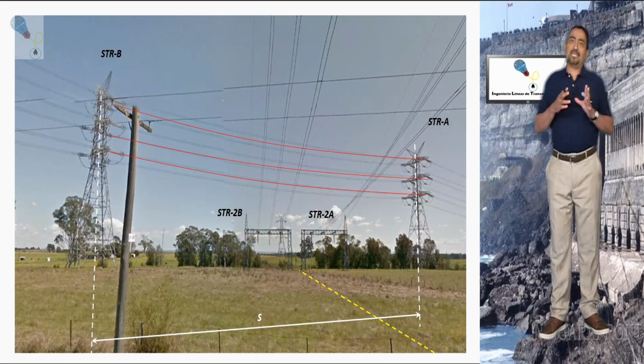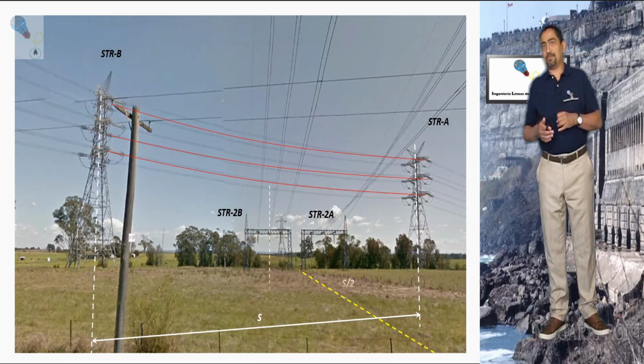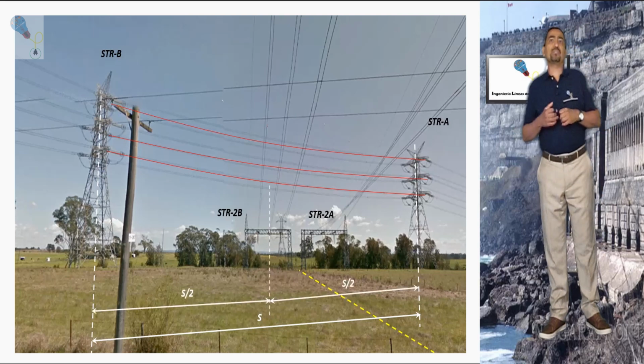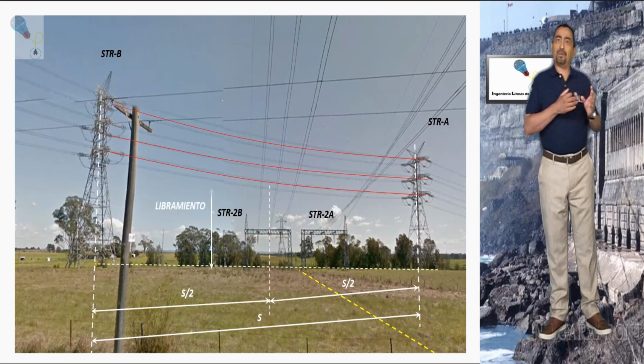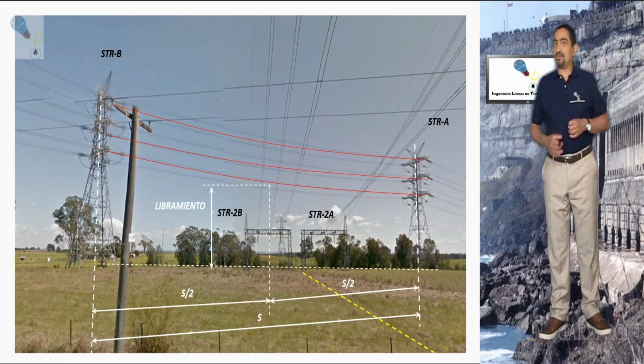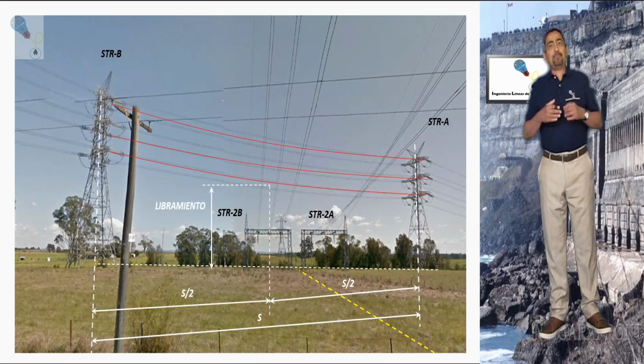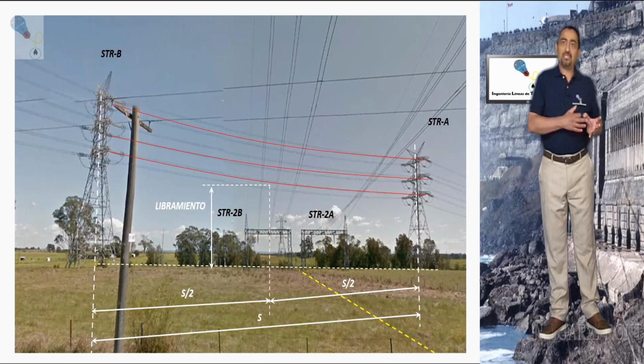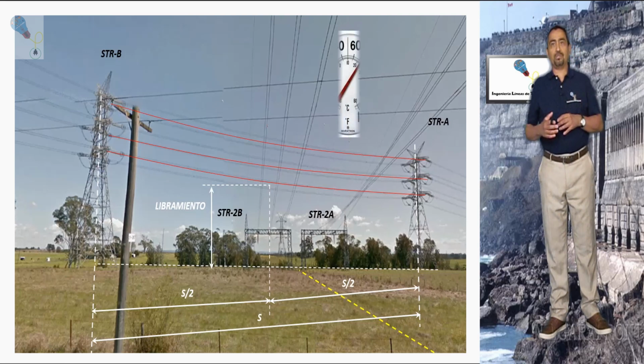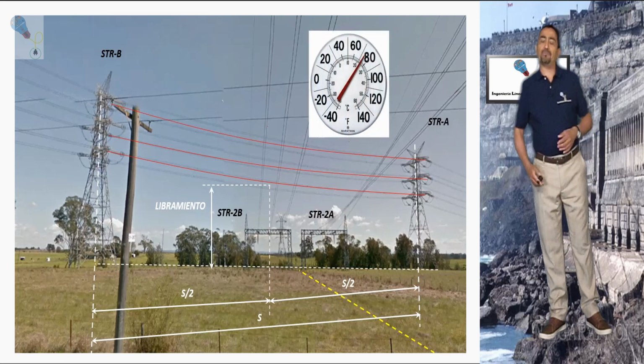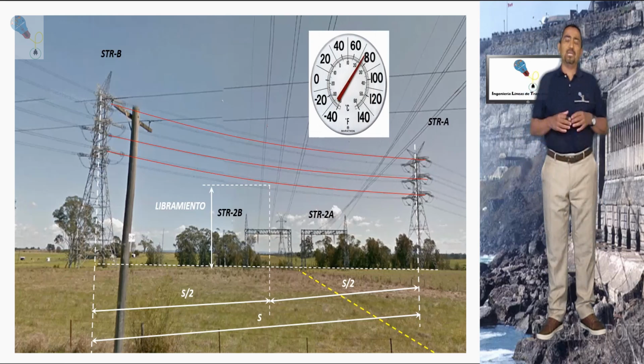Now, these last data — ambient temperature, date and time — are of vital importance to build up the thermal calculation data of the conductor cables. The ambient temperature is not the same as the real temperature of the conductor, due to the effect of energization.